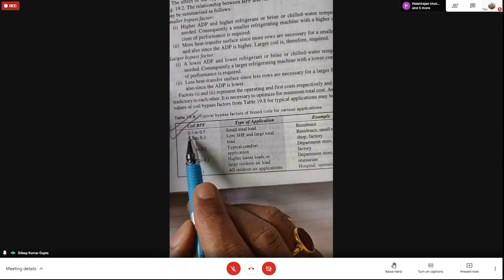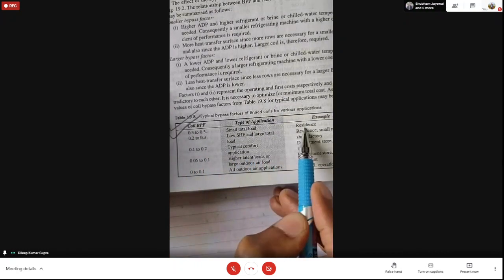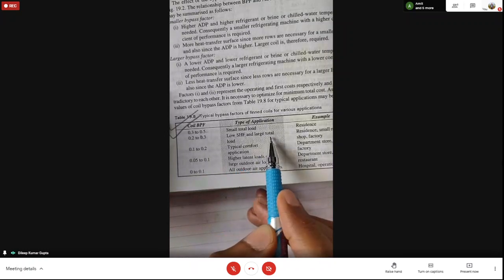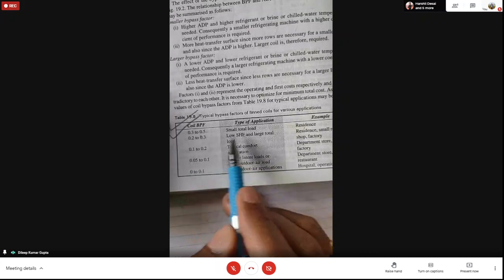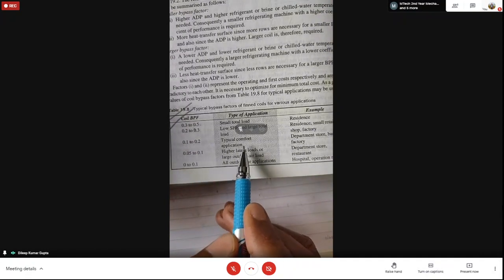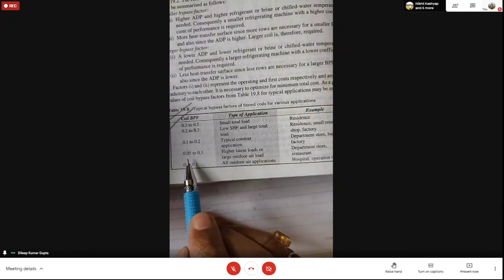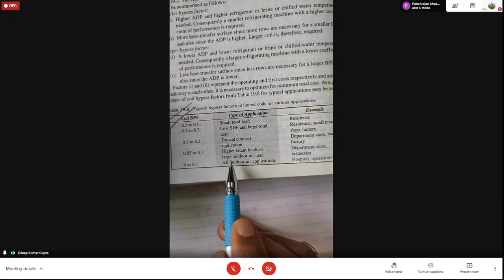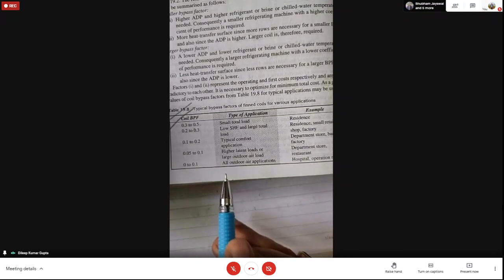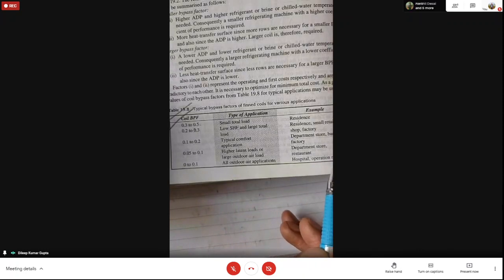You will get the value of the bypass factor for different applications. We'll refer to table number 19.8 for typical values of bypass factor based on application. You can see here this one. Generally, the bypass factor range varies from 0.3 to 0.5 for small total load in residential application. If you go for low sensible heat and large total load, the range is 0.2 to 0.3. This is for residential, small retail shops and factories. 0.1 to 0.2 for typical comfort application for department store, bank, factories, etc. 0.05 to 0.1 for high latent heat load or large outdoor load conditions, department store and restaurant we take. 0 to 0.1 for all outdoor air applications like hospital operation theaters and all.